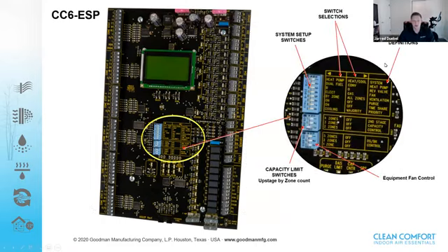Just a close-up of those dip switches. This is how you're going to configure the system. Purge, that's one that's on both the 2, 3, and 6-zone panels, or all the panels. That's a 60-second purge of the air out of the ductwork for a zone that has finished calling. You can turn that on or off.